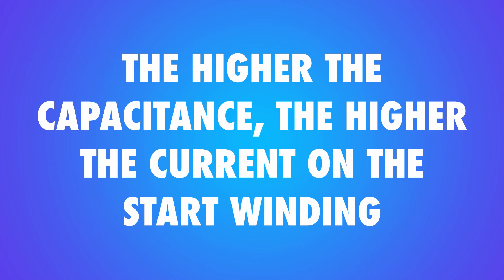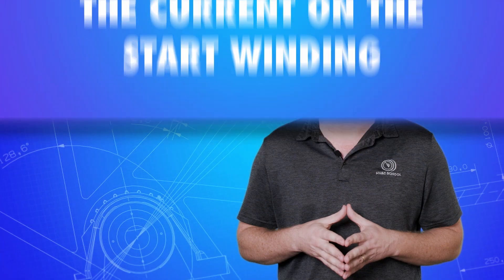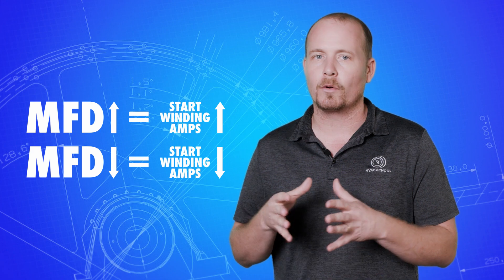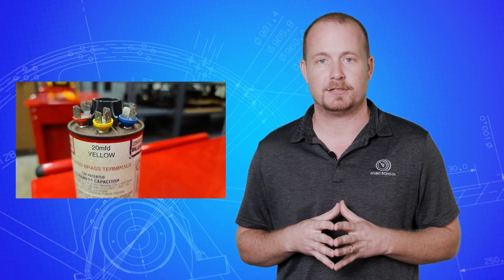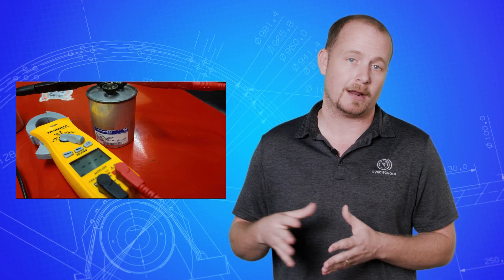The higher the capacitance, the higher the current on the start winding. On a properly wired PSC, or permanent split capacitor motor, the only way the start winding can have any current move through it is if the capacitor stores and discharges. The higher the MFD or microfarad of the capacitor, the greater the stored energy and the greater the start winding amperage. If the capacitor is completely failed with zero capacitance, it is the same as having an open start winding or an open circuit altogether. Next time you find a failed run capacitor with no start capacitor, read the amperage on the start winding with the clamp to see what I mean.